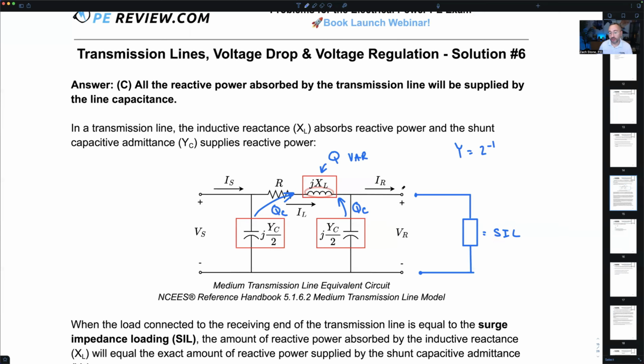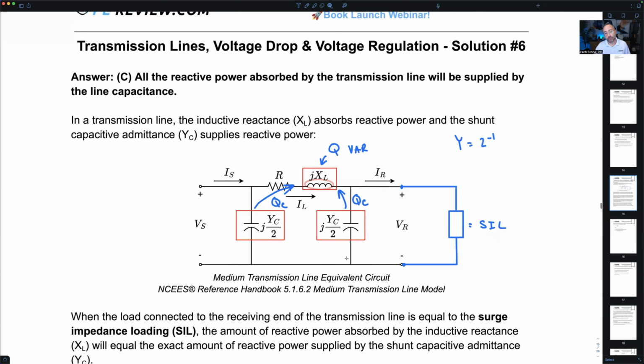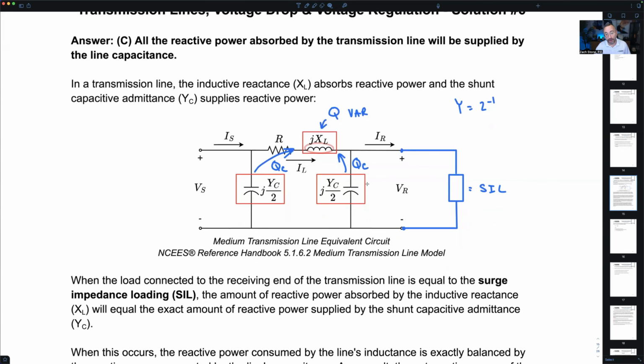So when the transmission line load equals exactly this value known as the surge impedance loading, then it's perfectly balanced in terms of reactive power. It doesn't need to consume any reactive power from outside the transmission line, or it's not producing an excess amount of reactive power that it ends up sending some reactive power to the receiving end. It's perfectly balanced from a reactive power point of view. Does that make sense? Kind of like how we talked about in the previous question, capacitor banks supply reactive power. Well, think of these as capacitors.